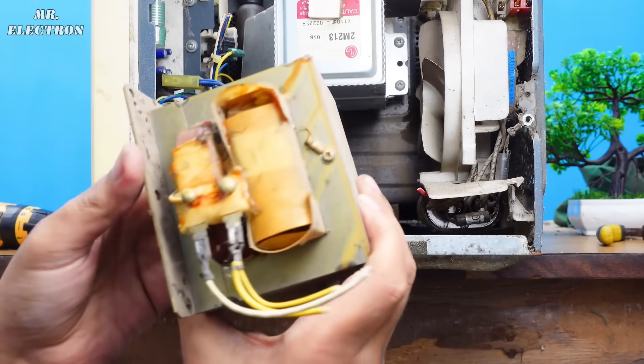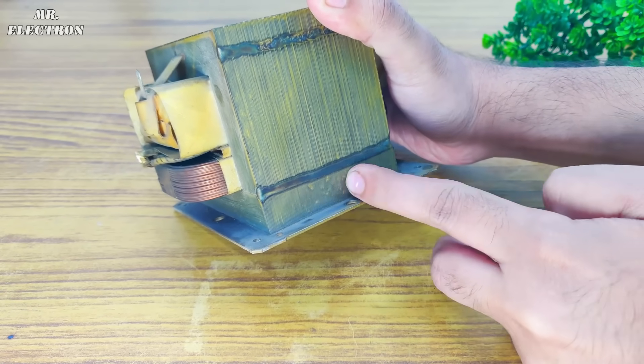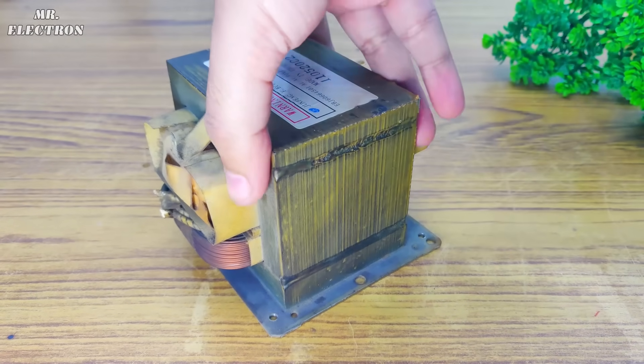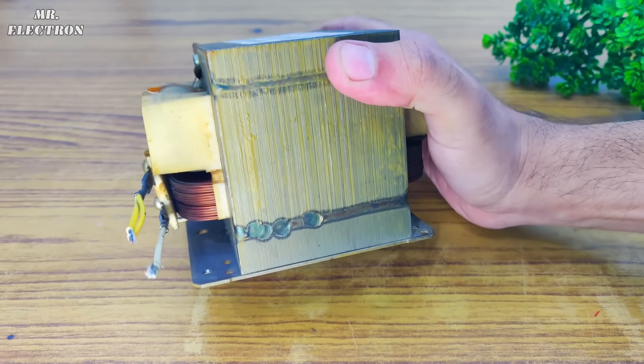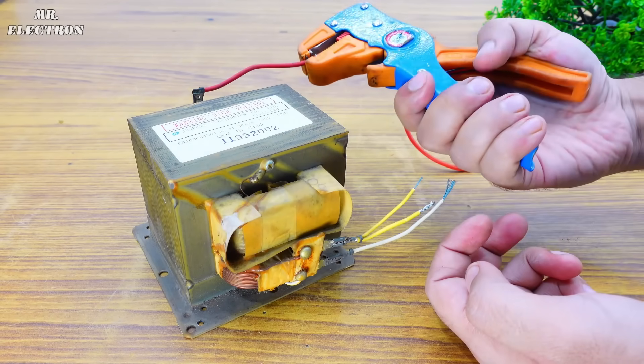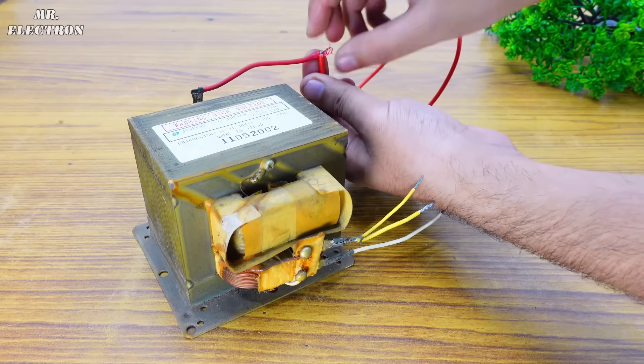It looks fine. Also here I'm showing you this core welding area which I personally do not like because it shorts up the silicon steel core and thus reducing the overall transformer efficiency. I'm not sure why these companies go for the welding process of these transformer cores.